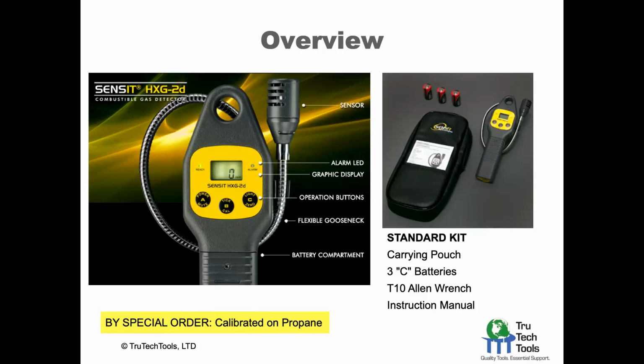So here's a quick overview. The product, mainly the ones we sell, are dedicated for methane. And methane is the major component of natural gas. And that's usually the fuel of choice, except in certain locales, where propane is being used. So if you request it, by special order, we can have one delivered that's calibrated on propane. And you'll see the subtle differences as we go through the technical aspects of this. It's the same unit, but it gets calibrated on a different gas.